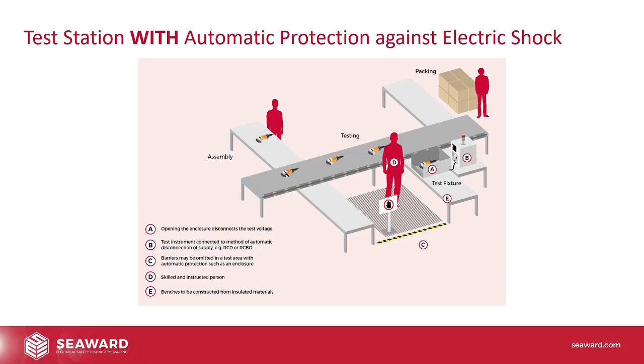I mean, this guy, if he's only making that one piece of equipment, he could have a test box there at point A that is the right size. If you were making all kinds of things at different sizes, or if you were working in the hire industry where you were testing everything that was coming back before hiring it out again, it's difficult to have an enclosure that fits everything. But again, we're just applying the same knowledge to the situation that we ourselves are in. But you can see at point A there, there's actually a transparent case on top of that. So there is a lid, and opening that lid will disconnect the test voltage.